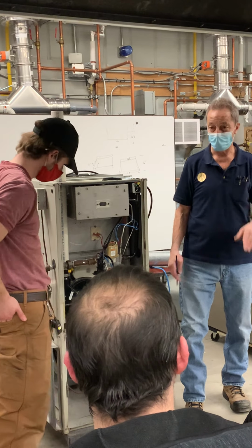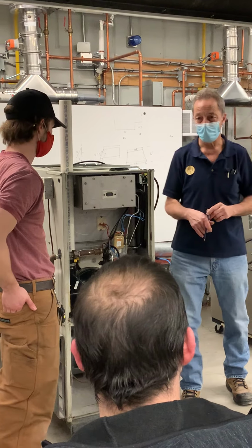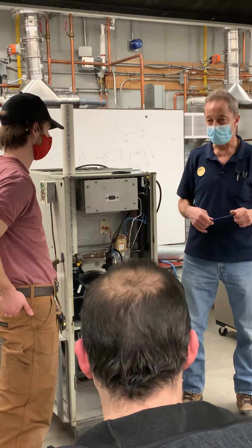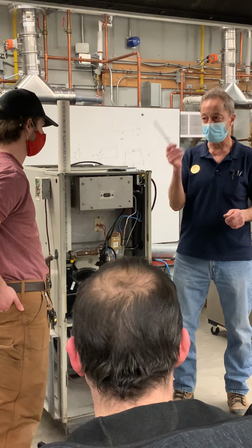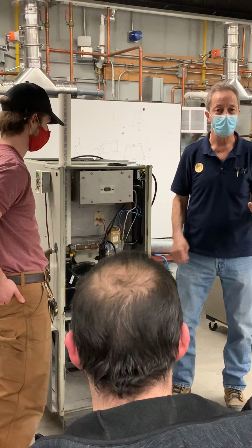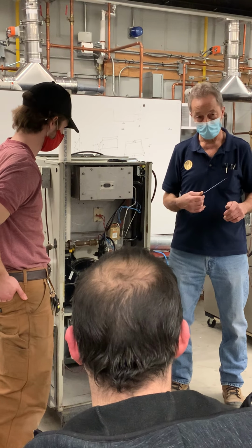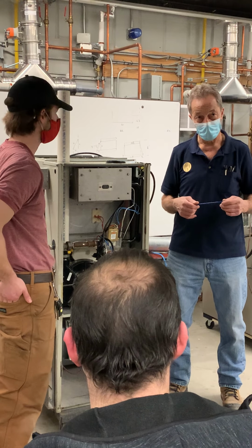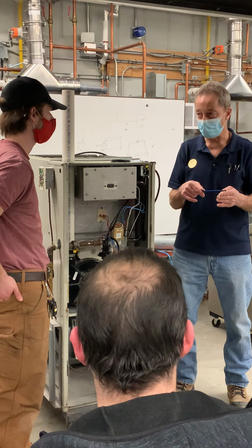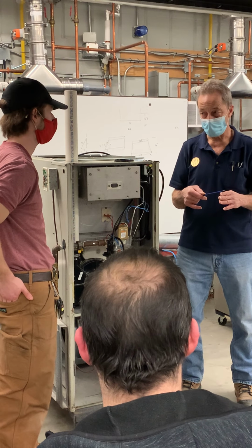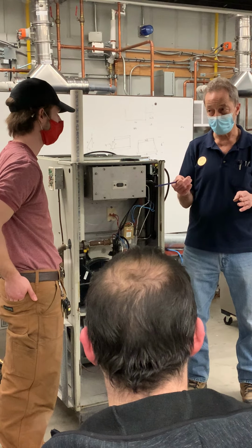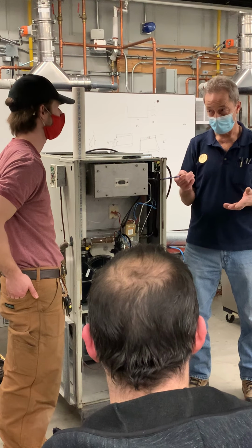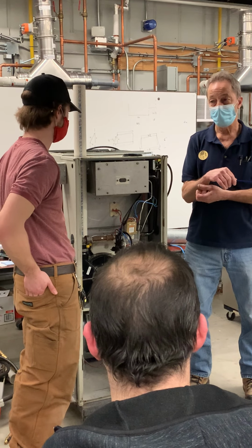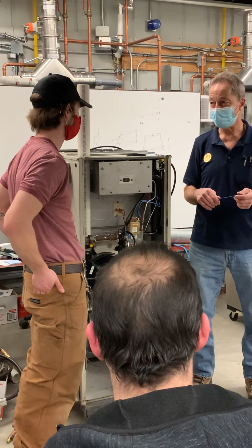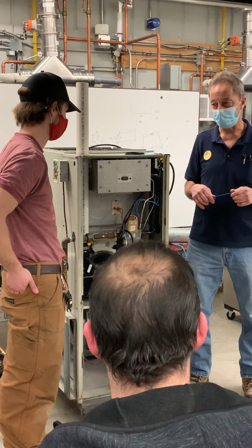Continuing on, so the HSI will shut off, correct? So the relay de-energizes, the contact opens, HSI shuts off. And then the main valve: now you can energize another relay, and that will open up the main valve. The contact closes, energizes the main valve, gas flows, and then it will ignite the main burners. Yes. What else happens?